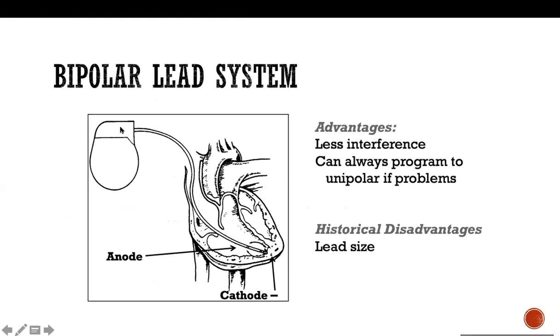Okay. So the electrical impulse goes from the device and then gets transmitted. If it's a bipolar, it goes from the tip and the electricity goes to the ring. So it's only those two areas. So you're delivering an electrical impulse into the myocardium. That's usually achieved by a specific amount of energy coming from the battery itself. So you don't want to give a high amount of energy because you're going to deplete the battery very quickly. So the minimal amount of energy you need is better. And you need an amount of energy that will be able to produce an action potential.